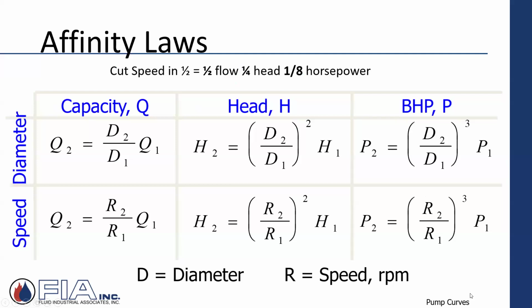In a nutshell, when you look at all three, and we look at, up above, they're talking diameter, which years ago was pretty common. You say, hey, I got this pump, it's way too big, it's oversized, overheaded. Take the impeller out, bring it downstairs. We have a pump shop downstairs here at FIA. We'd put it on a lathe, we'd do some calculations. Okay, what should we trim off the impeller? And now it's going to perform differently.